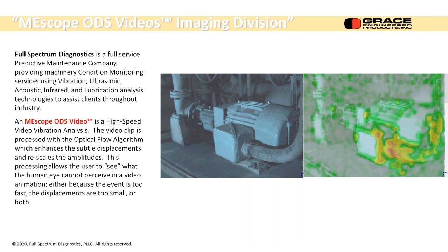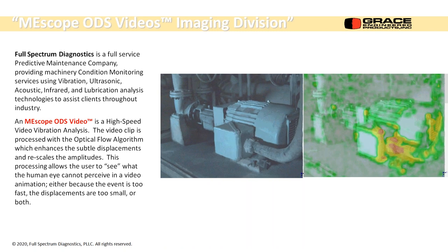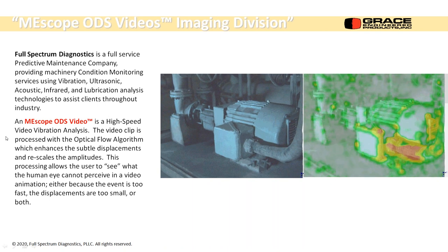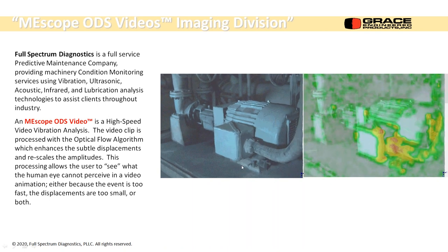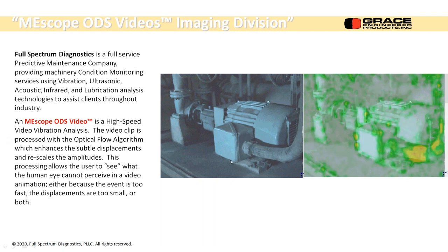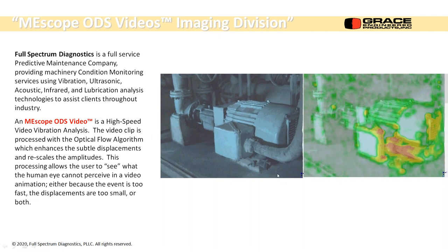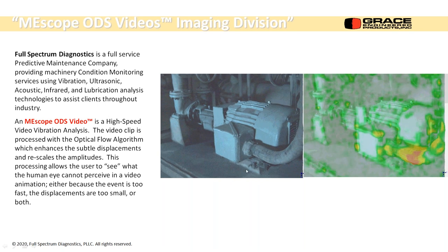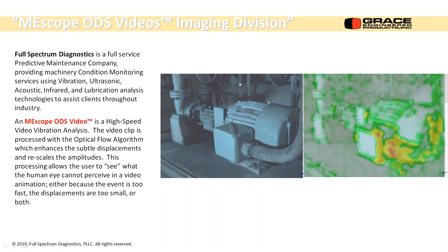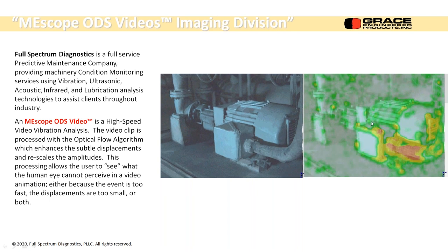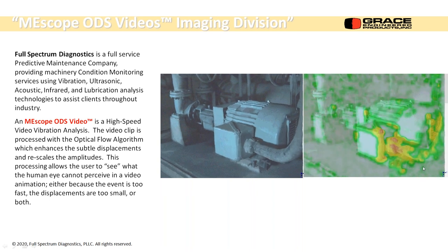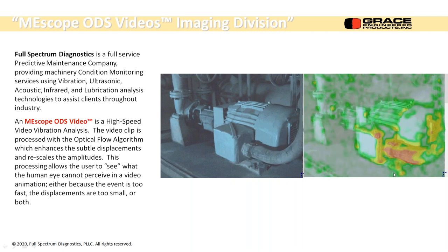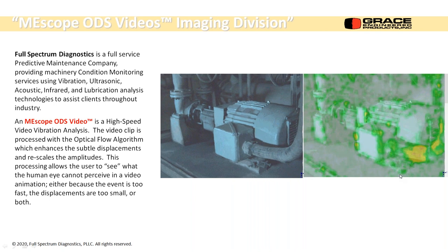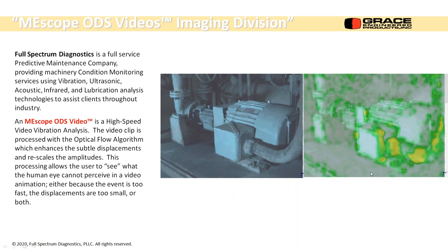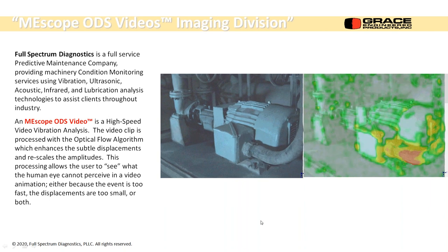So here you can see there's some type of problem in the machine. It's moving awkwardly. What it turned out to be, I'll give you a short version of this, is there was a problem in this foot of the motor, of the structure under the foot. This base plate was grouted in, a big C channel or I-beam channel around the outsides. They pumped grout in. It delaminated from the base plate, so it was lifting. So you get this kind of diagonal vibration going in there, and put a little color on it. This should be all gray down here. There shouldn't be any color to it at all. That just tells you that there's some motion there. So the only way we found this was with a vibration video, which was very interesting.